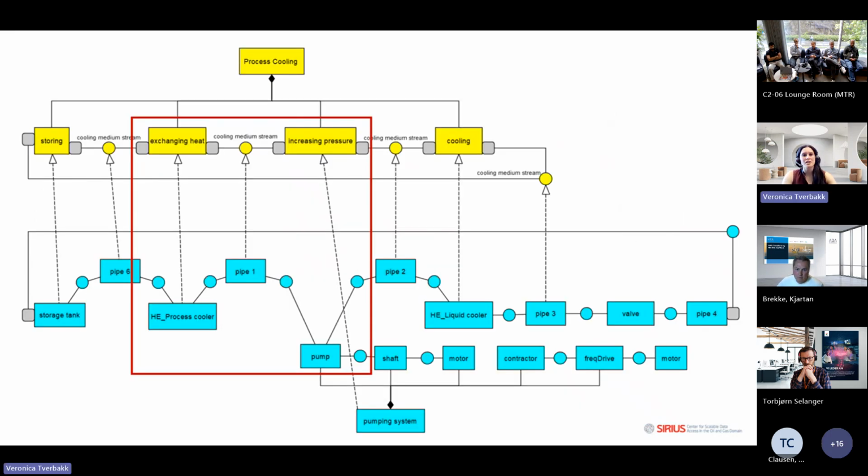In addition to this, an advantage is that you can run consequence analysis. So at the top of this drawing, you see that we have representation of the functional aspect. And on the bottom, we have the product aspect in blue. And we can see if a function fails, how many other functions are affected by such a failure? How many other pieces of equipment could potentially fail, right?